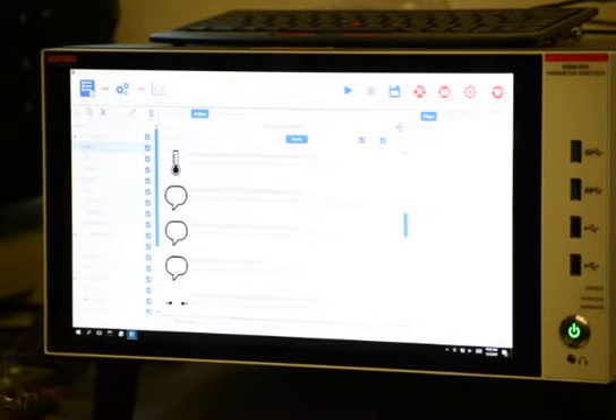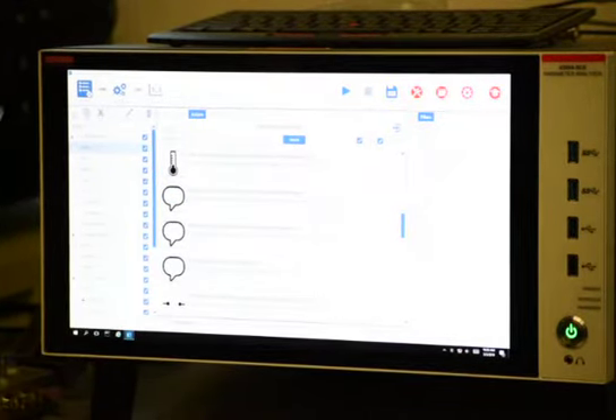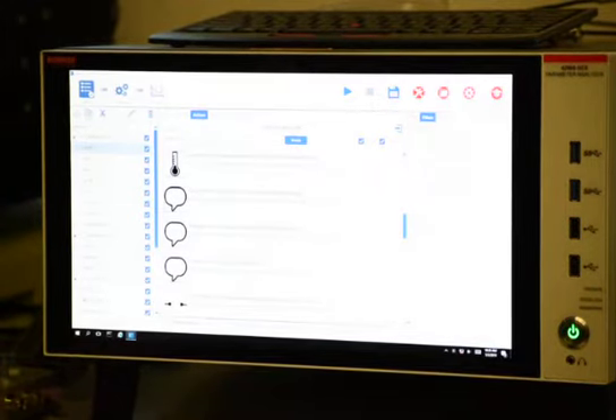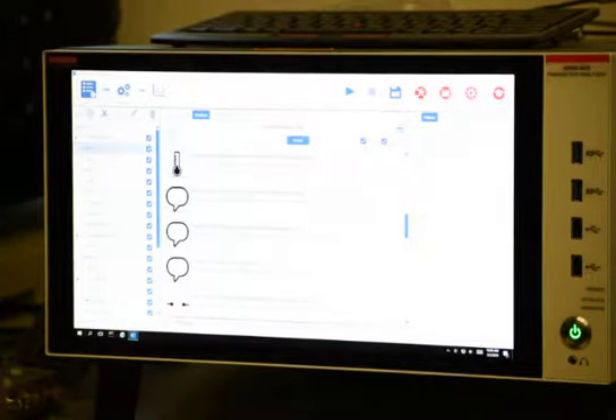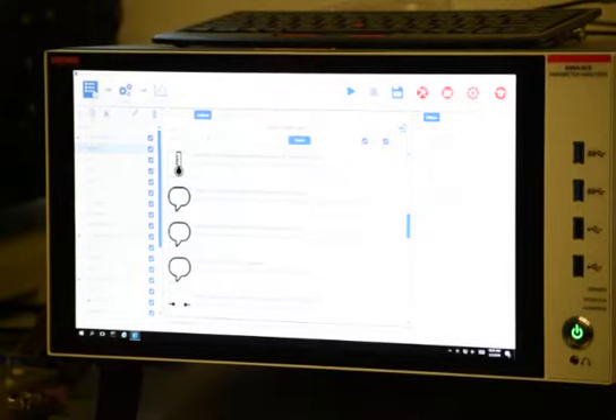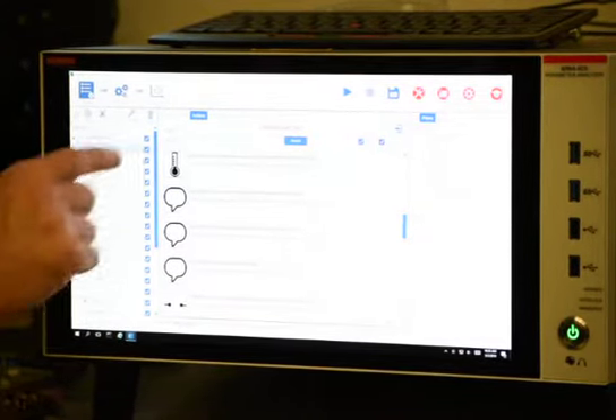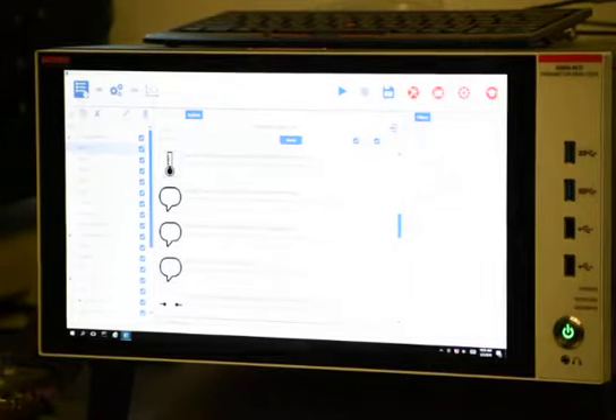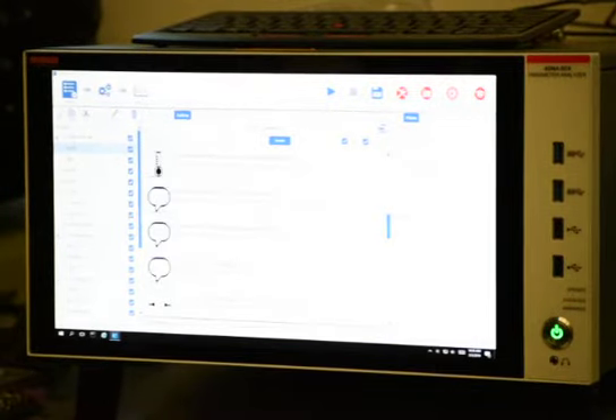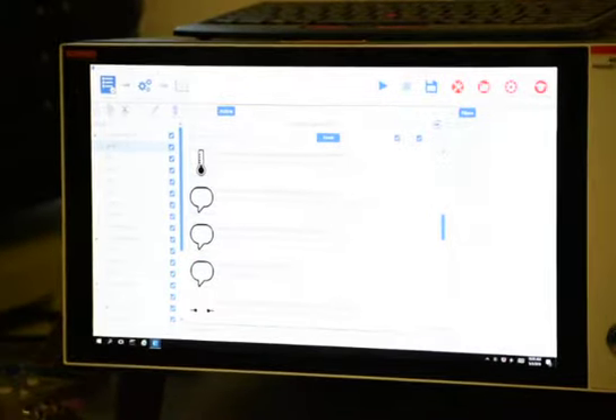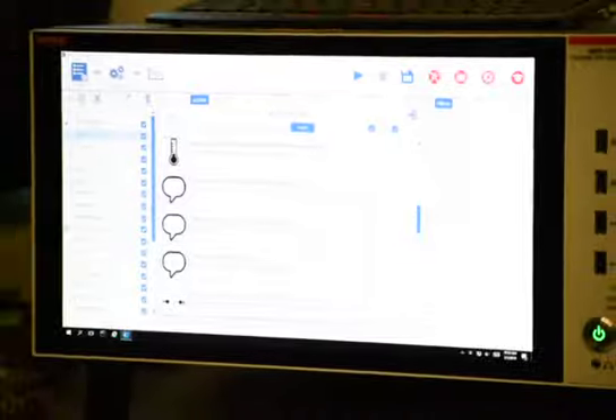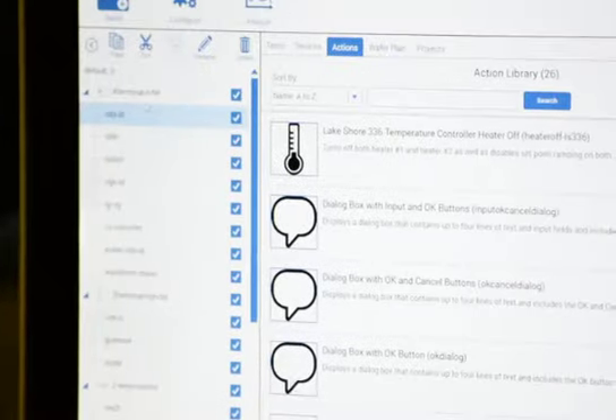But for instance, if I want to control some other piece of equipment, say a cryo chamber or an oscilloscope or a heated chuck, whatever, I can write a test that I can insert in here, and I can have them both checked, and I can run them both sequentially, right? So I can have a characterization, set a temperature, characterization, set a temperature, characterization, and I can run them all sequentially. And in the test for the temperature chamber, you can even have soak times built into it. So you can hit run and walk away for the weekend, and then when you come back, you'll have all your data.